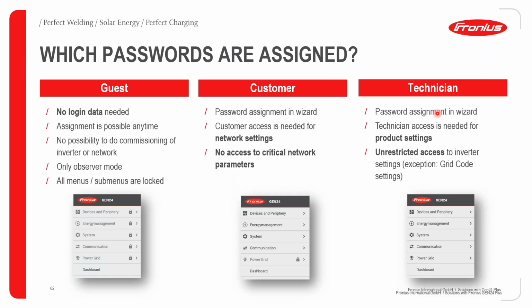The next stage is the technician setup, where you also get a password assigned. The technician section gives unrestricted access to the inverter settings, except the grid code settings. For the grid code settings, if you require access, we do require that you get an access code from our tech support in Austria.